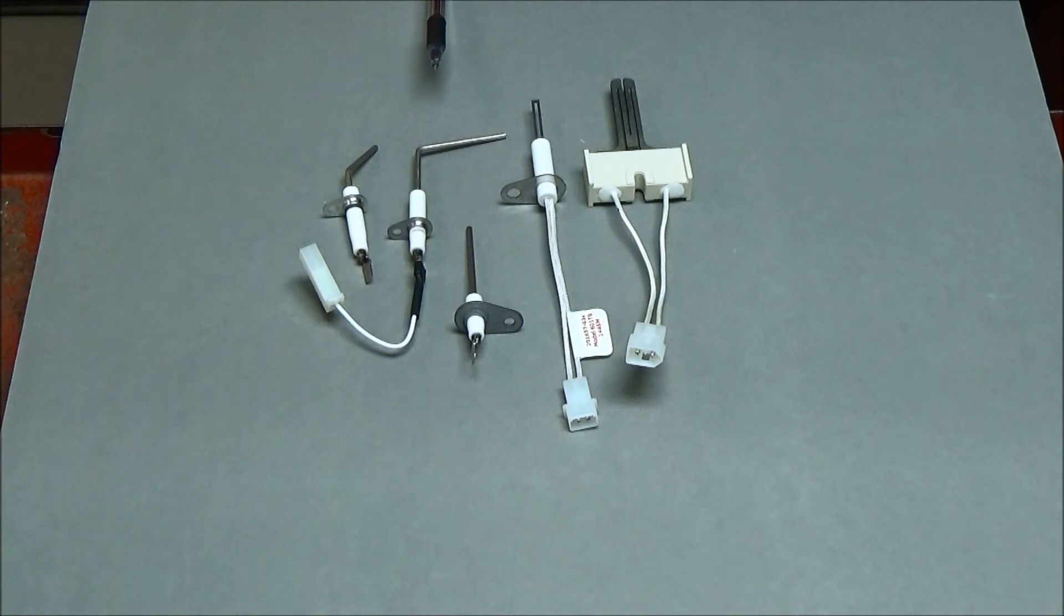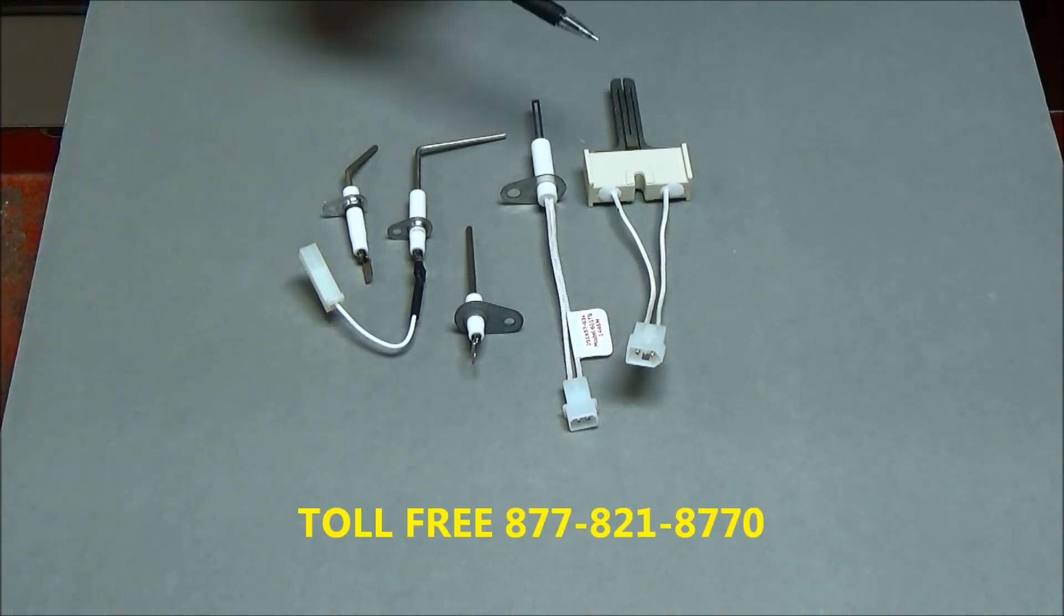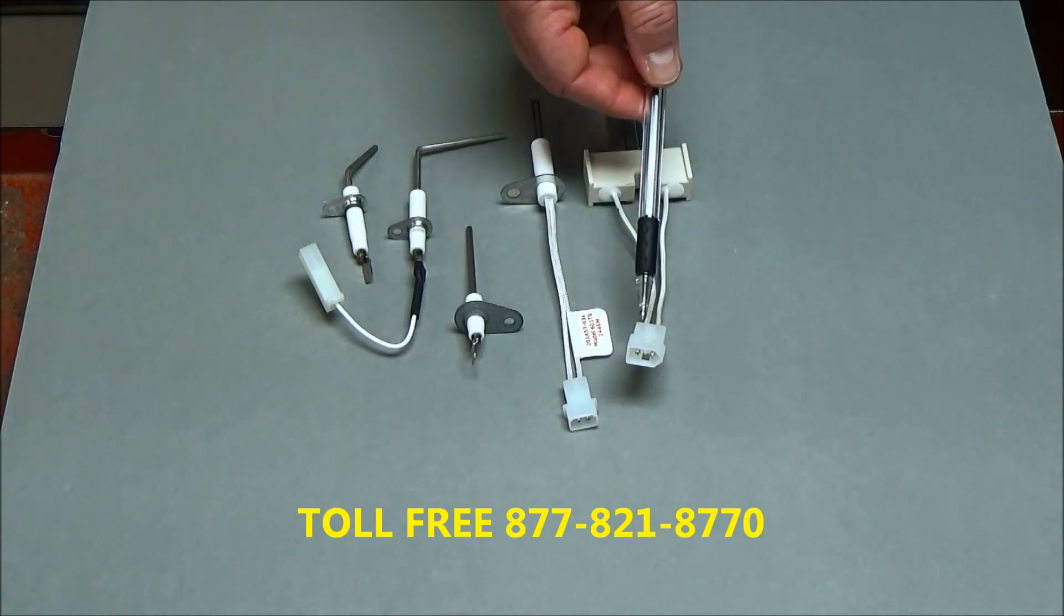Issues we see with igniters include cracks right across the middle. They're very difficult to see, but you'll usually see a little white powder around them. The best way to check this igniter is to take a meter and go in these ports with your meter leads.